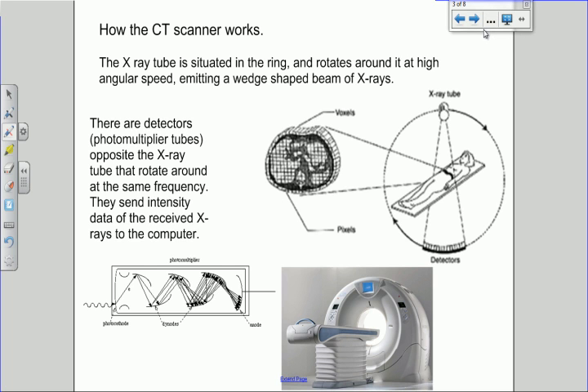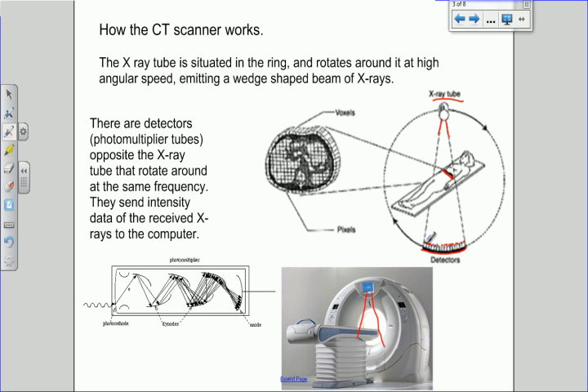In this ring is the kit used to produce the image, which consists of an x-ray tube that produces a wedge-shaped beam of x-rays passing through the hole in the middle where the patient lies. The slice of the patient will be exposed to the x-rays. Some of those will be absorbed by the patient, and on the other side of the ring is a bank of detectors covering that wedge-shaped area. These detectors detect the intensity of the x-ray at various points as it comes through the patient, and that intensity information is sent to the computer, which builds up a picture.